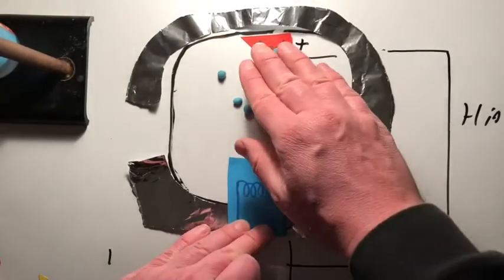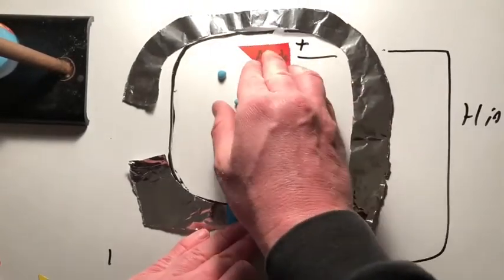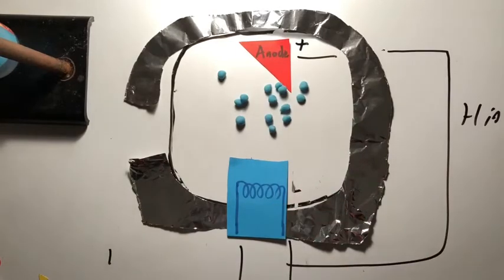Boom, boom, boom. Now the vast majority of them will hit the anode, and their energy is just going to be converted into heat. That's one of the reasons why we use tungsten. It's got a very high melting point. But we're still going to need a kind of coolant system. So usually it's going to be oil that'll come in and bleed away a lot of the excess heat.